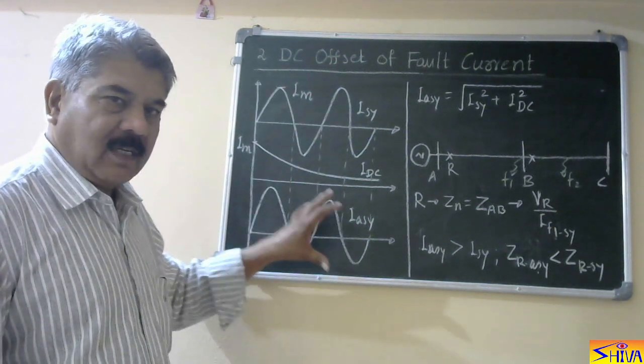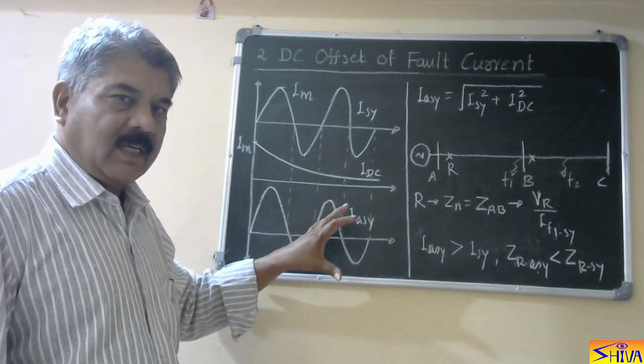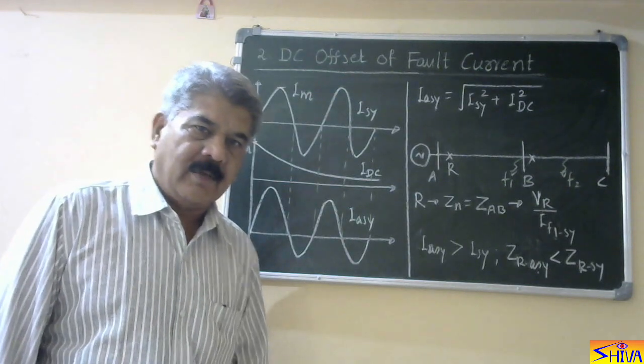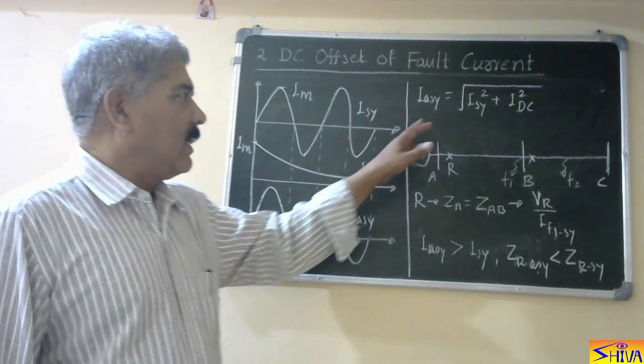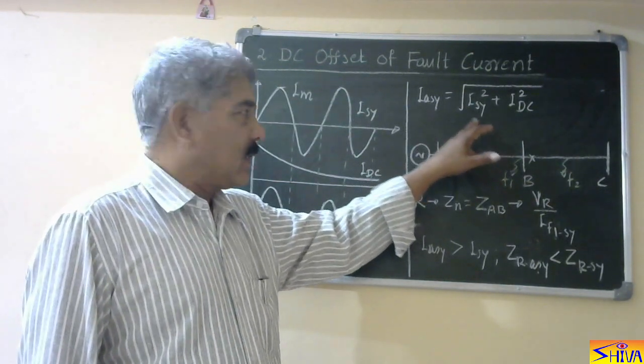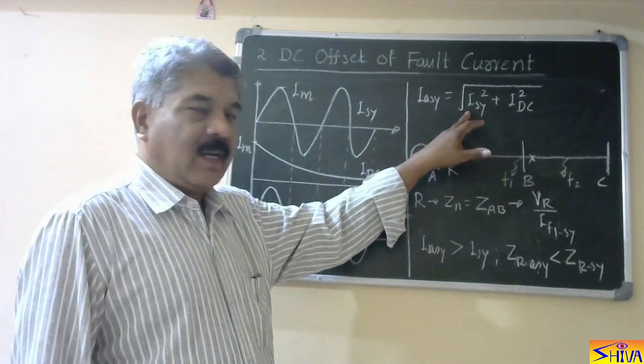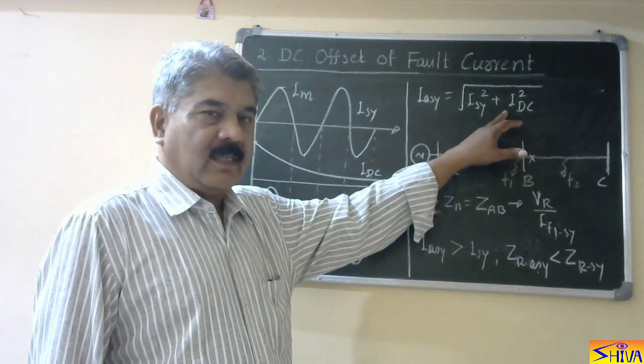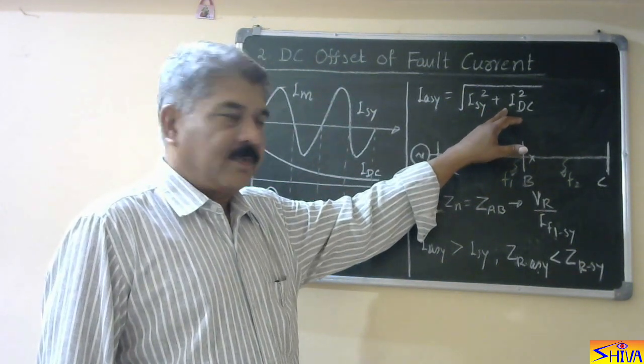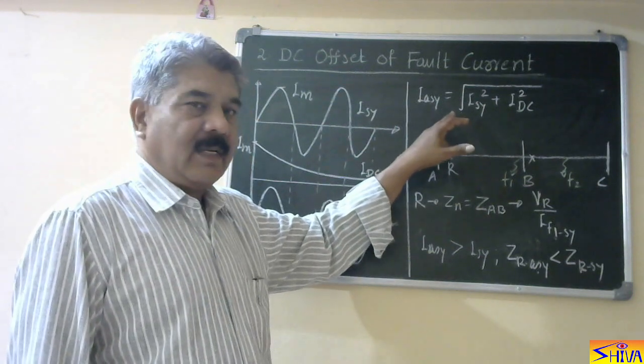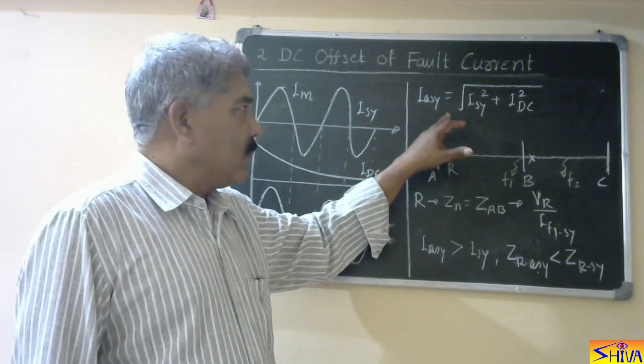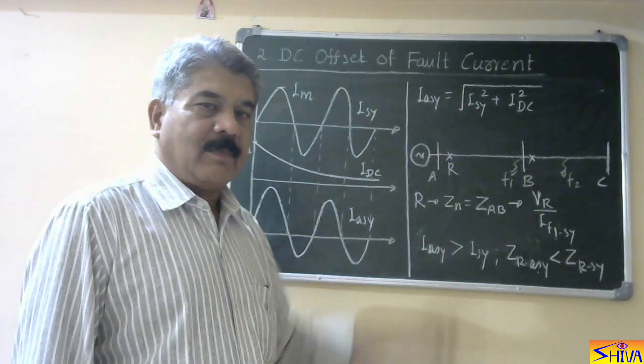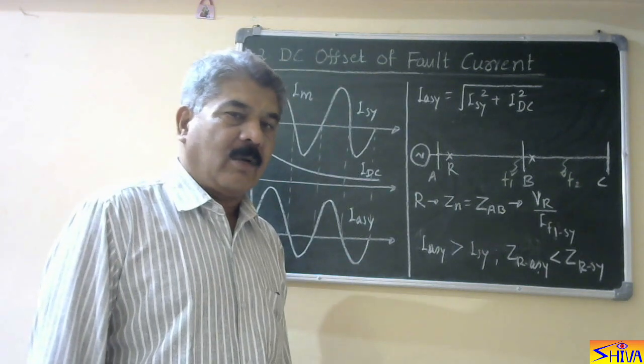The overall magnitude of this asymmetrical fault current is greater than that of the symmetrical fault current alone. It is obtained by the equation: square root of (symmetrical fault current squared plus DC offset squared). Here, the asymmetrical fault current magnitude is more than the symmetrical component of the fault current.